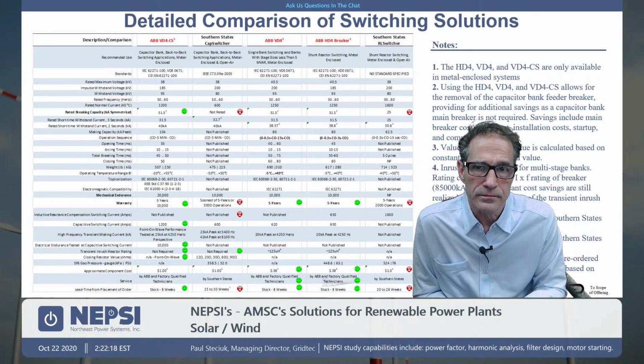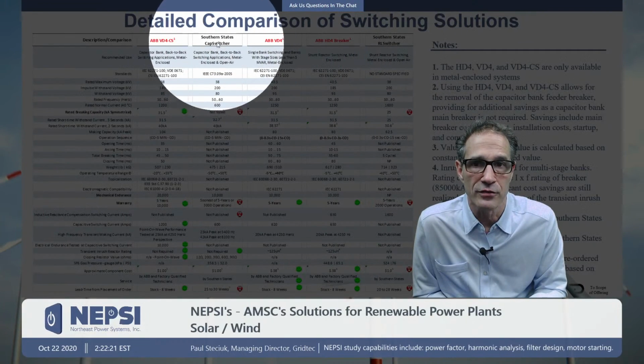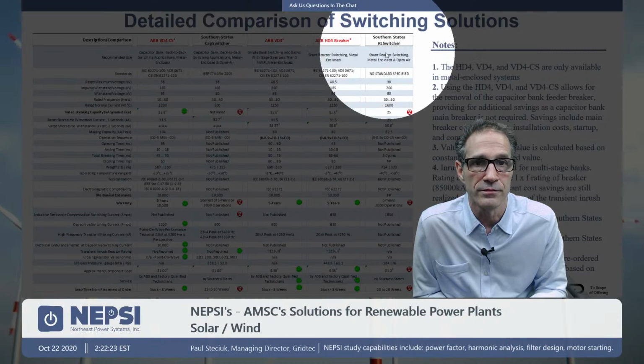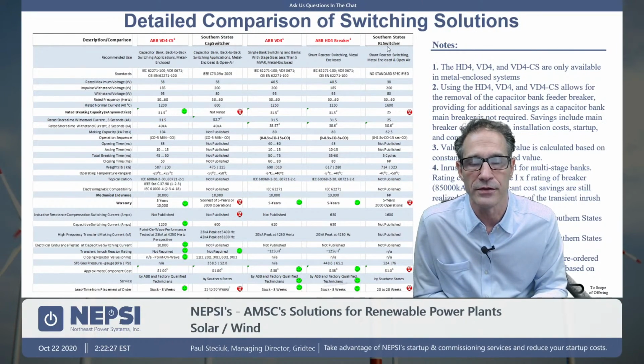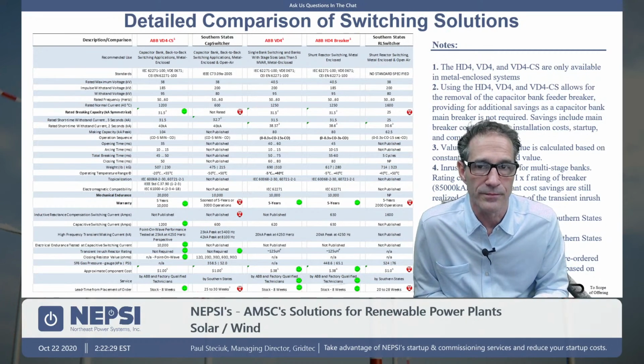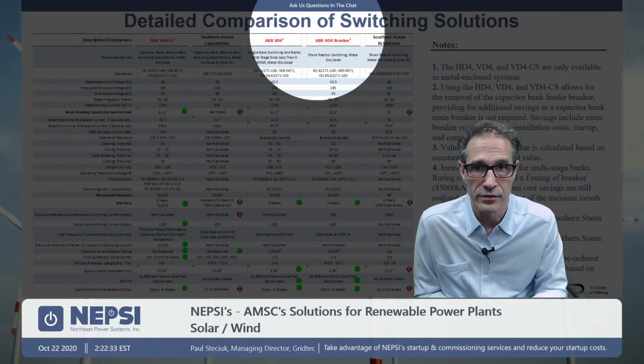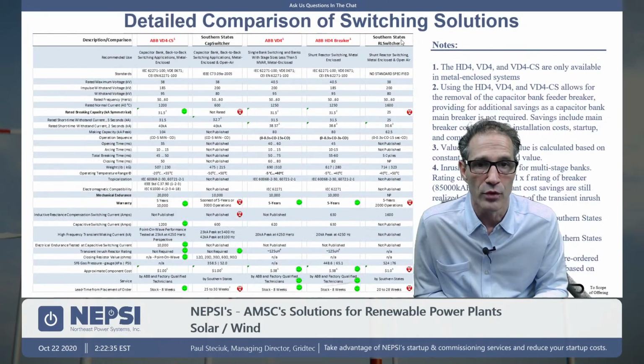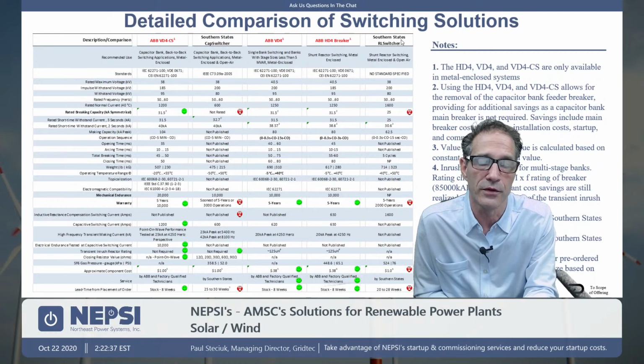So the Southern States cap switcher is an outdoor rated device, and the Southern States RL switcher is also an outdoor rated device. The breakers are indoor. So if you specify outdoor rated equipment, you are forced to use that technology.